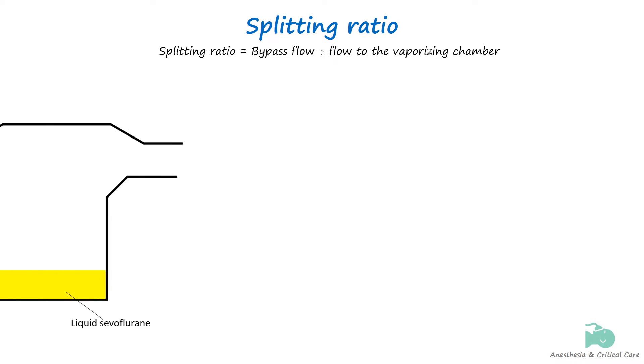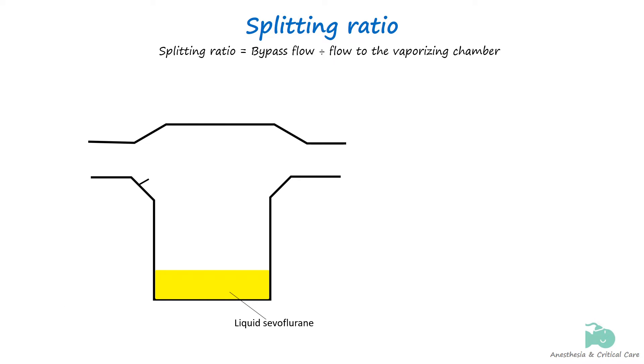Let's begin with this simple vaporizer containing sevoflurane to understand how splitting the fresh gas changes the percentage of delivered anesthetic. The saturated vapor pressure of sevoflurane is 157 mmHg at 20 degrees Celsius.